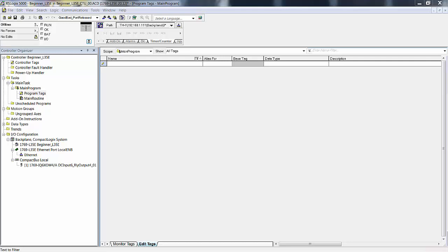Emphasis on this: there is not a count up data type and a count down data type. There is just a counter data type. And the instruction either increments the value in the accumulate member of the counter data type, or it decrements the value in the accumulate member of the instance of that data type.